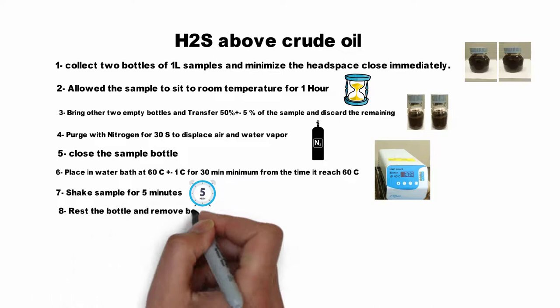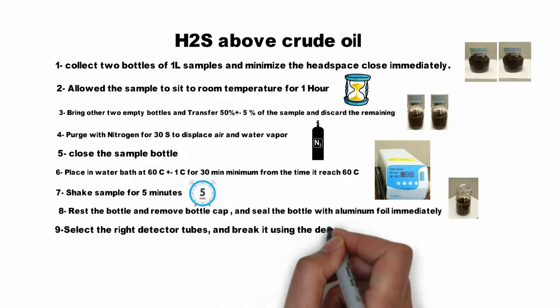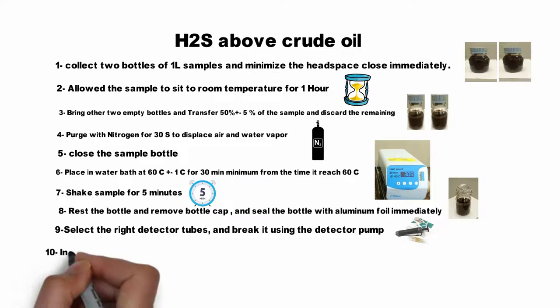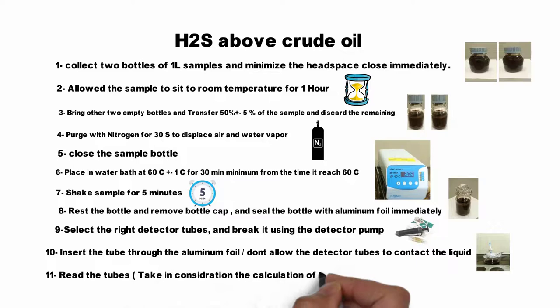Select the correct detector tubes and break them using the detector pump. Insert the tubes through the aluminum foil, taking care not to allow the detector tubes to contact the liquid phase. Read the tubes and take into consideration the stroke calculation — for example, full or half stroke.